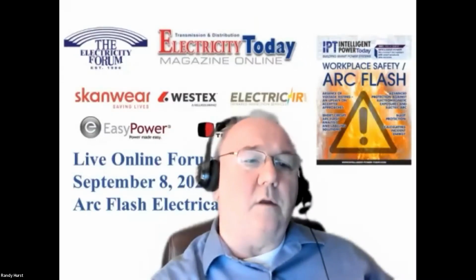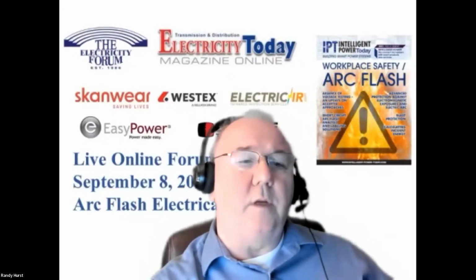Does a cotton undergarment, under the Arc Flash rated clothing, provide additional protection? It doesn't provide additional protection from an Arc Flash, but cotton is quite a good insulator. So it would insulate the body from a bit of the heat created by the Arc Flash, but it's not to be used as part of a layering concept to increase the Arc Flash value of the outer garments. Whatever your last layer of Arc Flash PPE against the body is, if you're wearing something underneath that, you've always got to go by the actual rating of the outer garment rather than adding a bit extra for an undergarment that might be cotton.